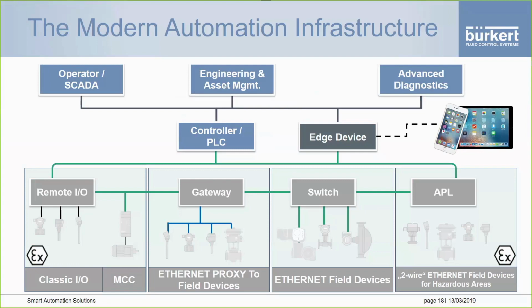So we generally use a computer-based edge device that reads through the data, sorts out what we actually need, and runs diagnostics. This happens acyclically - we're not scanning diagnostic data every few microseconds, but at a much slower rate depending on need. Things like asset management data, such as ID number or last calibrated date, won't change even on a one-day basis, so it doesn't need to be scanned that often.